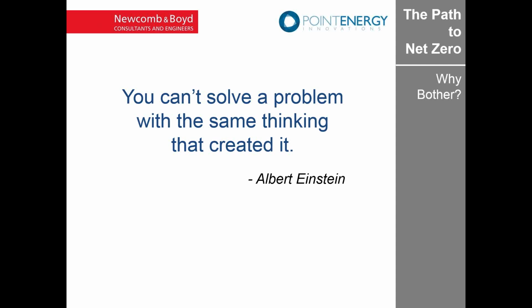The pumps were half the size of normal pumping, and the contractor was convinced it wouldn't work. When they flipped on the system and it didn't work—it was a school project—he went running to the principal, and I got a call from the principal. It had been a long time since I got a call from a principal. I went rushing down there, and it turned out the chiller was airlocked. Once they got the air out, these pumps that were half the normal size worked great. In fact, we measured the flow, and our 20% safety factor was in fact delivered, and the system worked great. So it's possible to do air systems as well as water systems at roughly half the pressure drop compared to what we typically see.